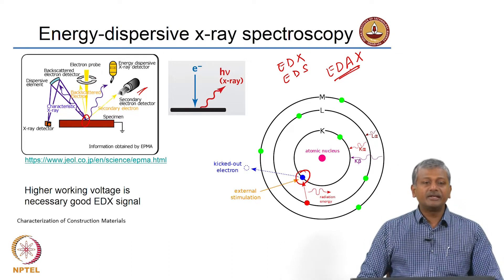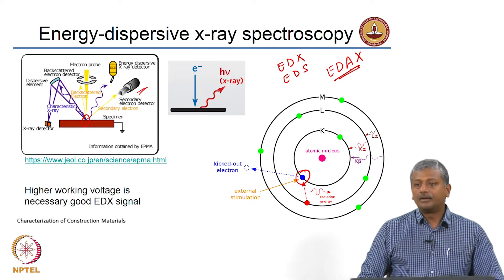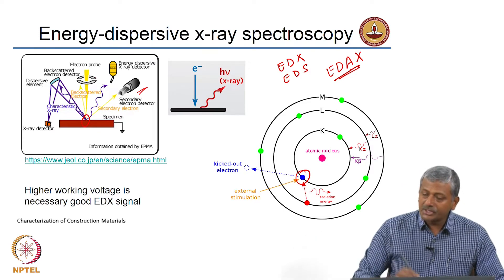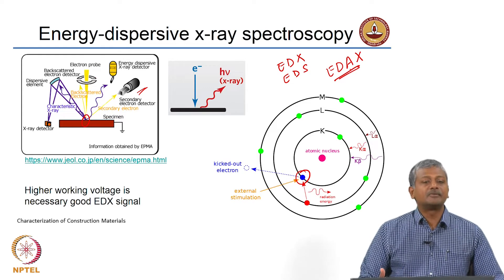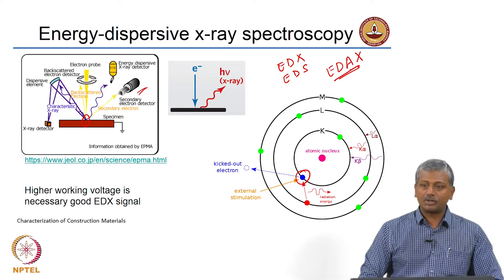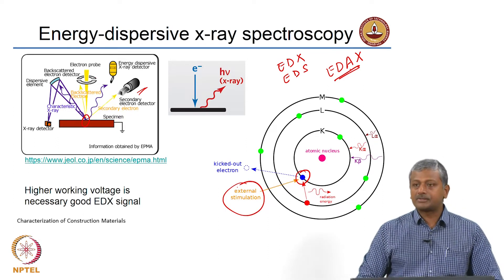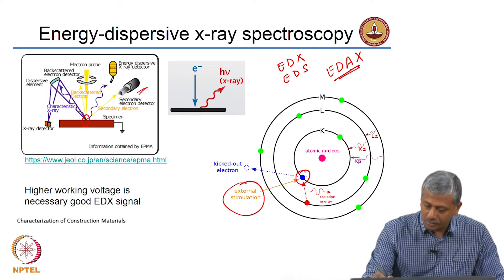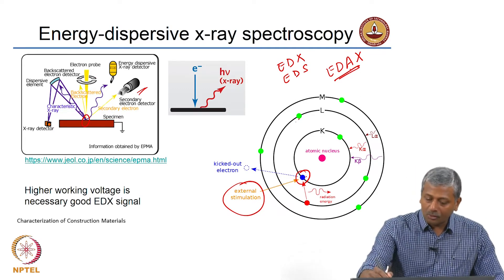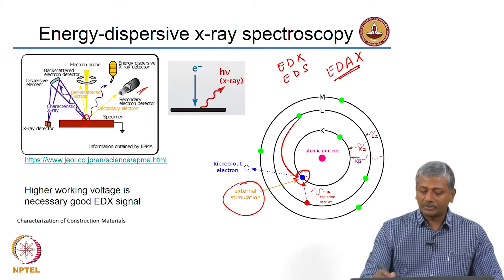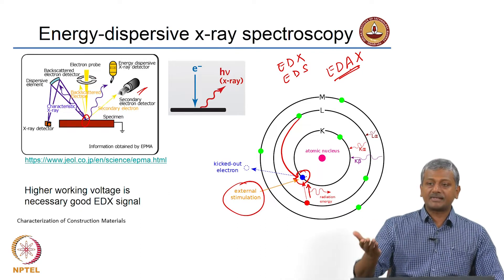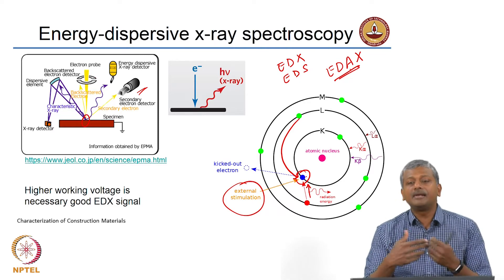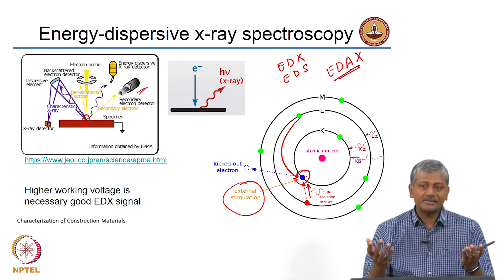The incident electrons are high-energy and can knock off the inner-shell electrons of the sample atoms — silicon or calcium, for example. This is similar to what happens during X-ray generation in an X-ray tube, except here the external stimulation is done by high-energy electrons rather than X-rays. When an inner-shell electron is dislodged, an electron from the next higher shell jumps in to fill the vacancy.